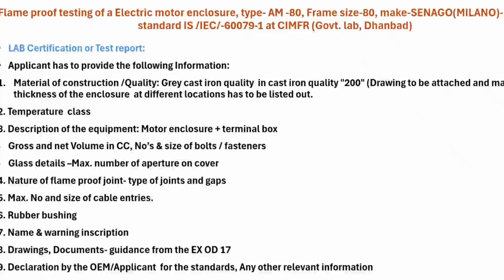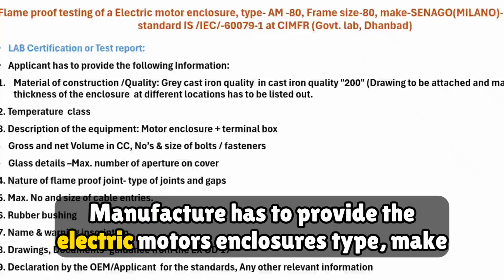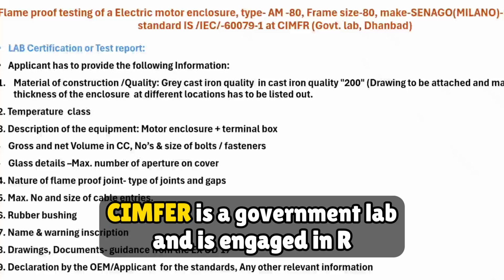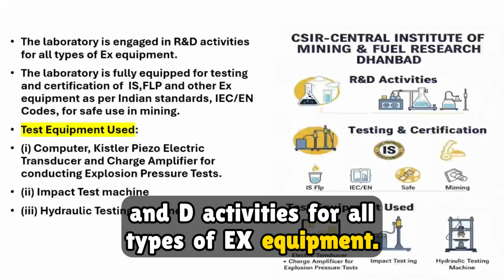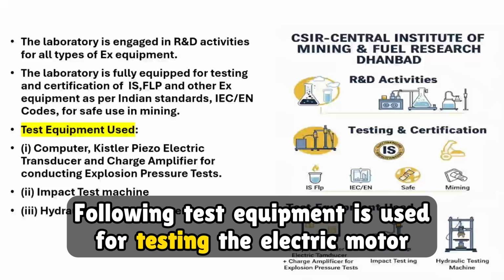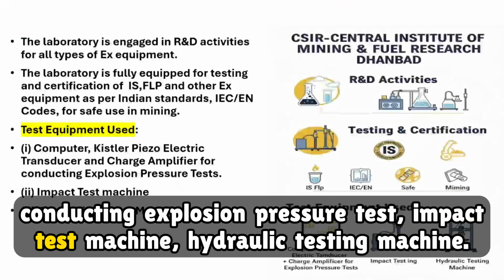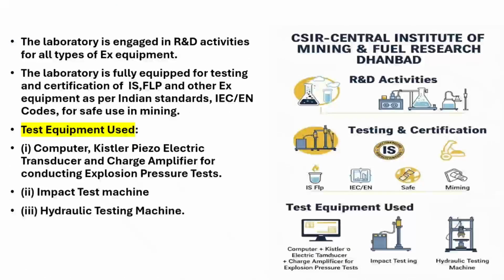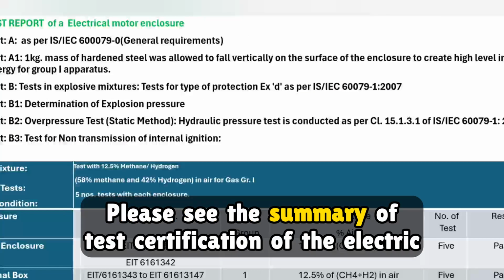Let us see the procedure to be followed by the manufacturer for FLP testing of an electrical motor at CIMFR lab. Manufacturer has to provide the electric motor enclosure type, make, and a declaration for the standard along with the relevant information as provided in the slide. CIMFR is a government lab and is engaged in R&D activities for all types of EX equipment. The following test equipment is used for testing the electric motor enclosure: computer, Kistler piezoelectric transducer, and charge amplifier for conducting explosion pressure test, impact test machine, hydraulic testing machine. Please see the summary of test certification of the electric motor enclosure.